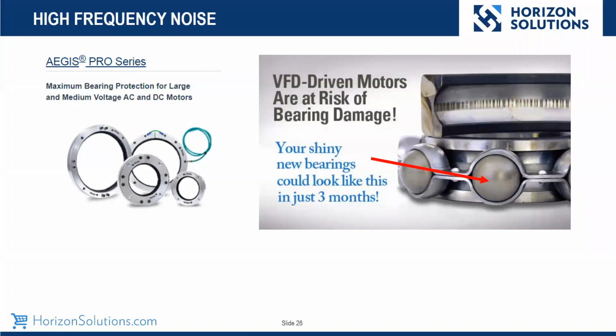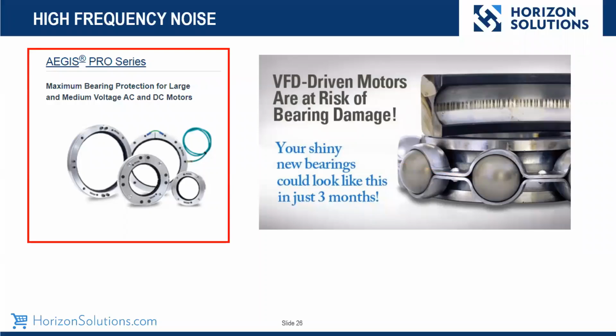That actually adds to the degradation of the motor also. A really quick fix is, when you order a motor, or you can retrofit it afterwards, to use the Aegis rings. The brush will make contact with the shaft, and then it will release those high frequency currents back out to the chassis, as we're going to show you in a second in a simulation of circulation on the shaft. Next slide.